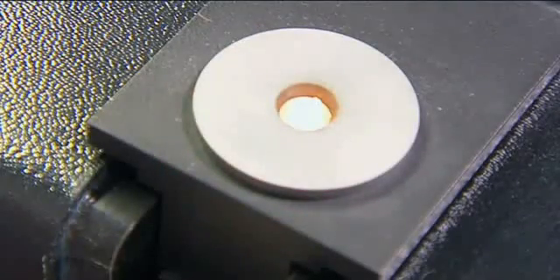Pyrolytically coated transverse heated graphite furnaces create optimum atomizing conditions even for demanding samples. The patented third-generation Zeeman-effect background correction works with a variable magnetic field and offers sensitive background correction with a doubled timing pulse frequency.